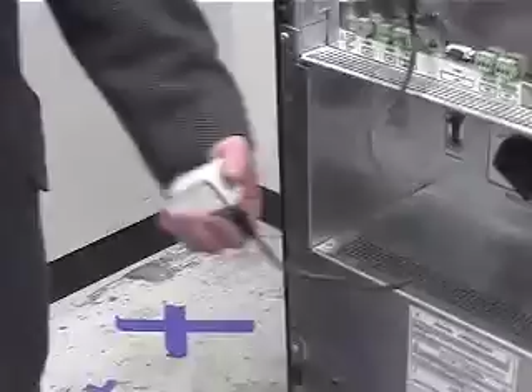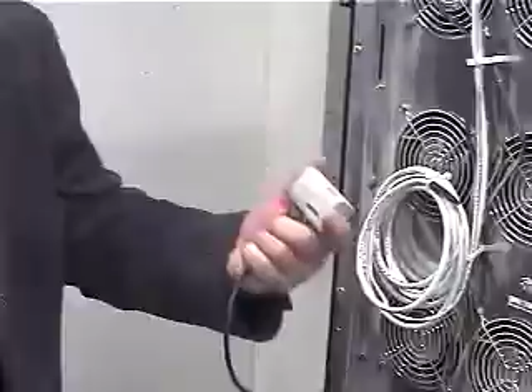This right here is an environmental monitoring program. It monitors temperature and humidity in this room, and that information is relayed back into this card. Once you're online with this, you'll be able to see the temperature and humidity in the room. You also have some dry contacts right down here, so if you had water or something in this room, you could tie a leakage sensor into this as well.